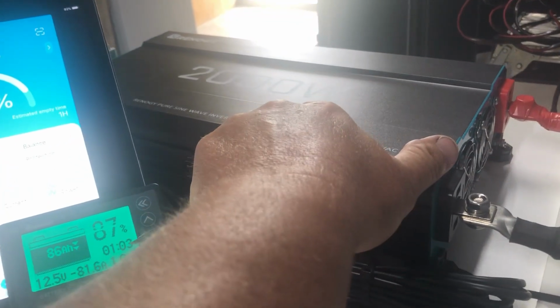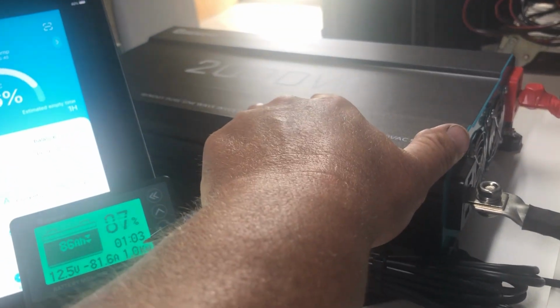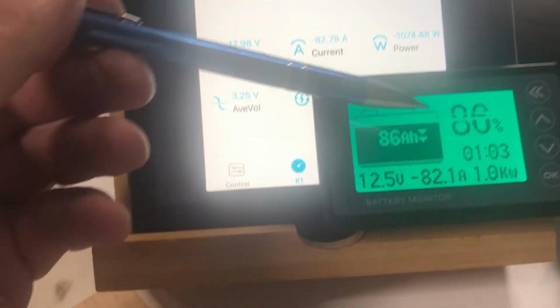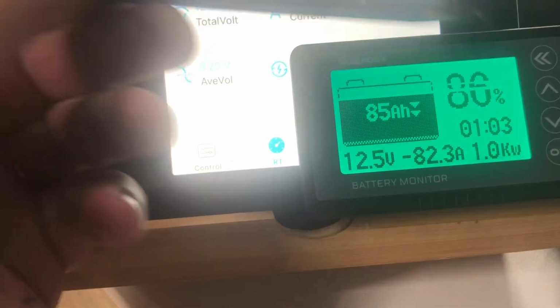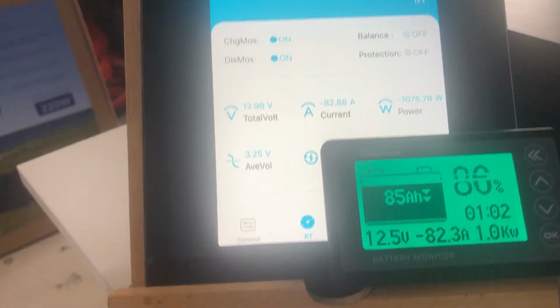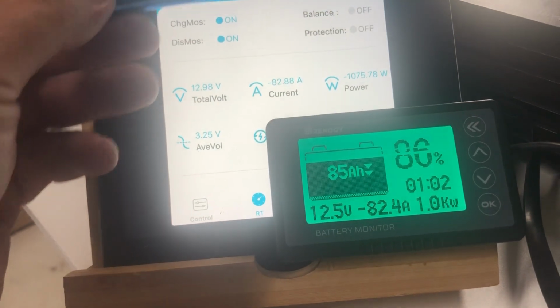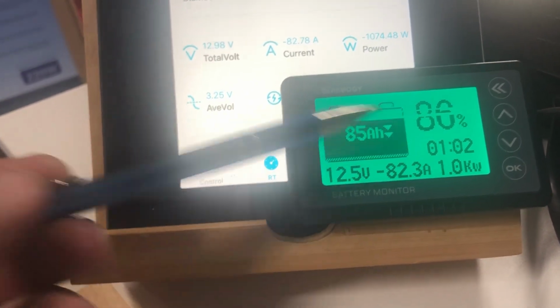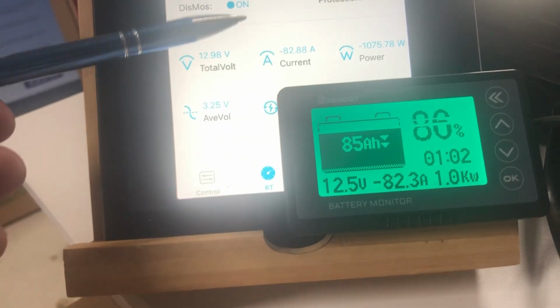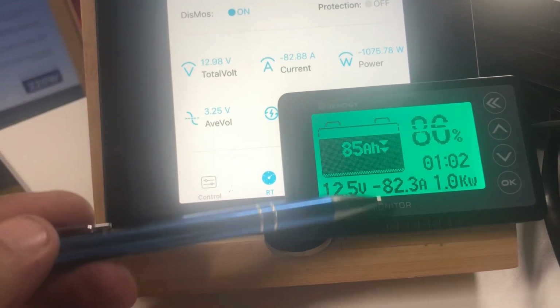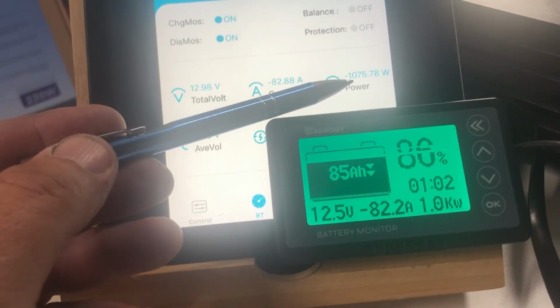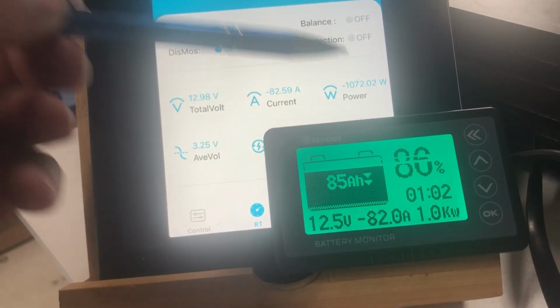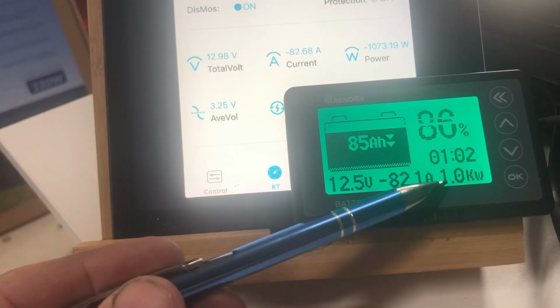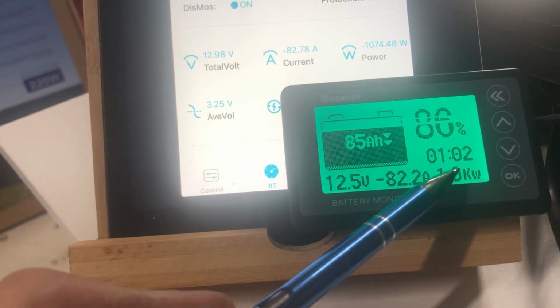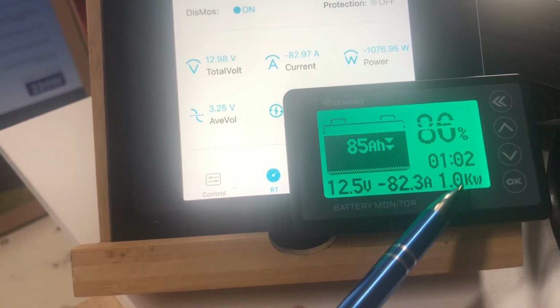So I've got a nice load now on the inverter. Let that settle in, and as you can see, we're down to 86%. We're showing 86% on the monitor and 86% on the BMS. Interesting, time to go is rounded to 1 hour here and 1 hour 2 minutes here. Current near enough the same, 82.8 and 82.3, and the only difference is the wattage output. We're going 1072 compared to 1 kilowatt, or 1000 watts even. I'd say that's a rounding thing with not enough digits on this display.